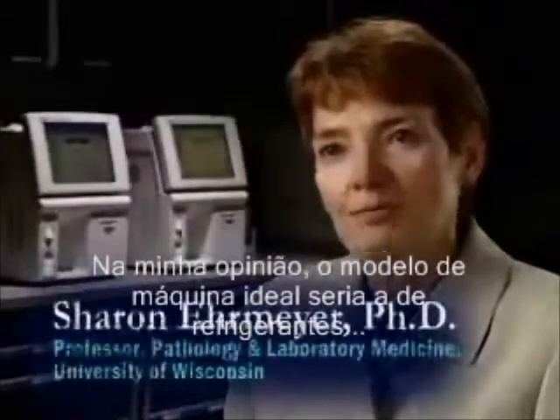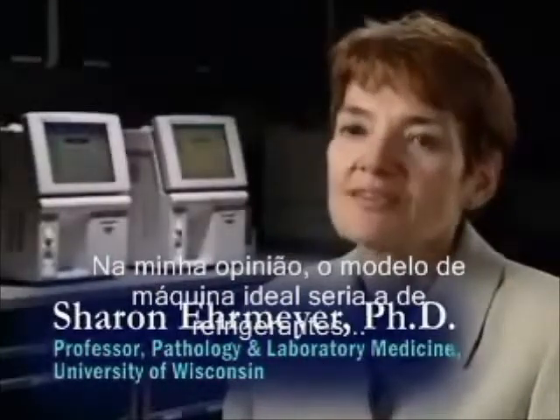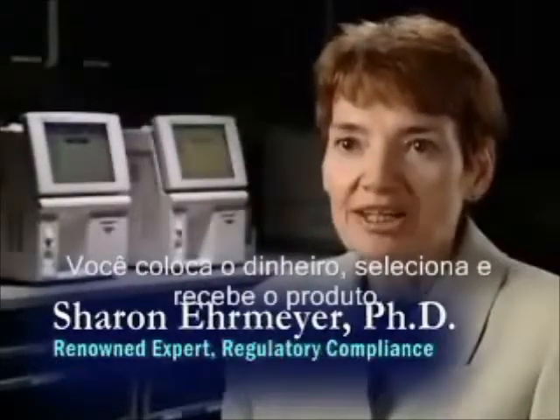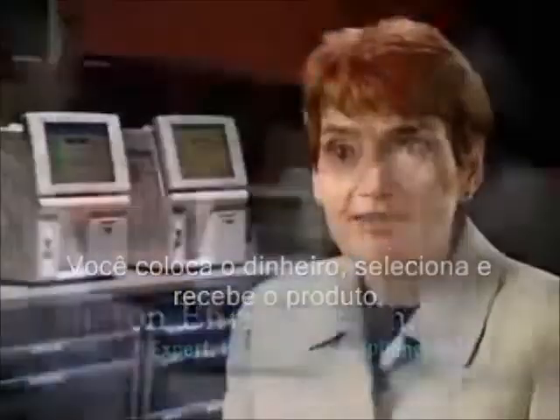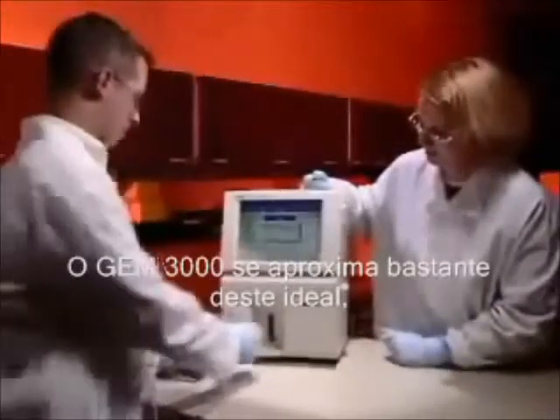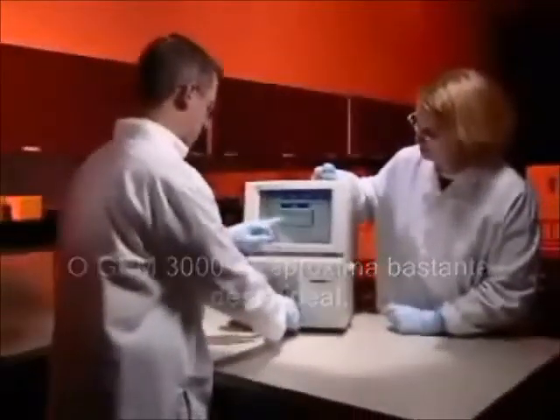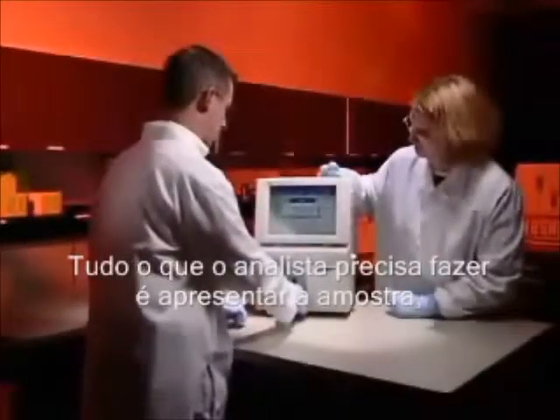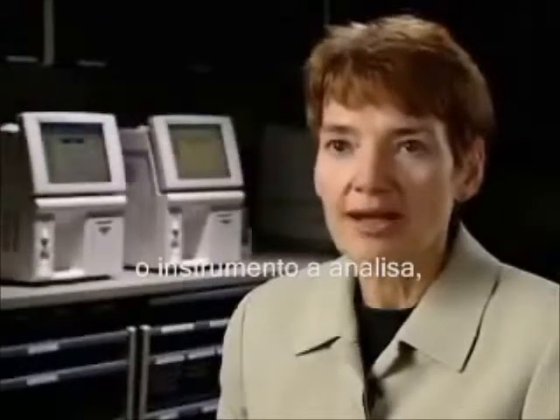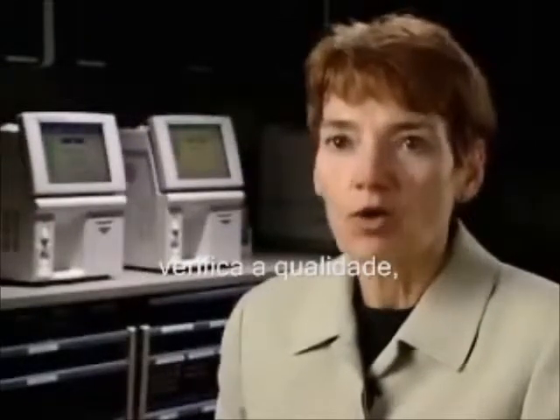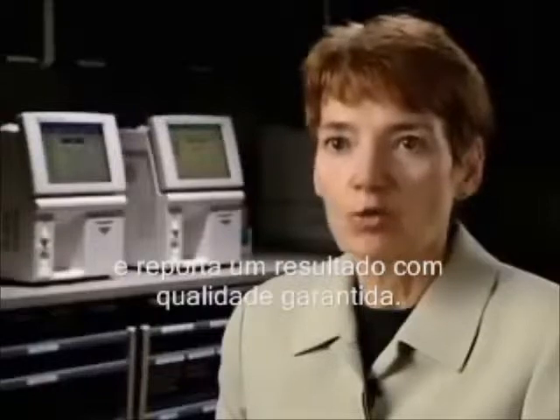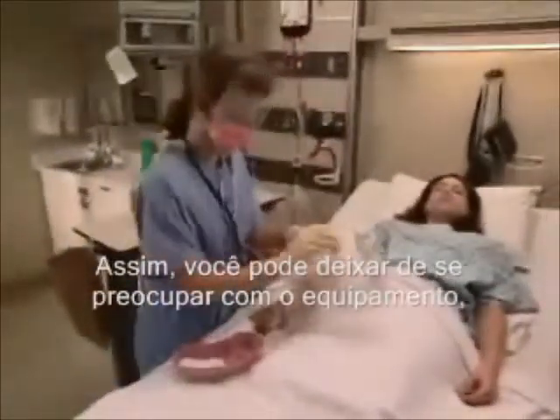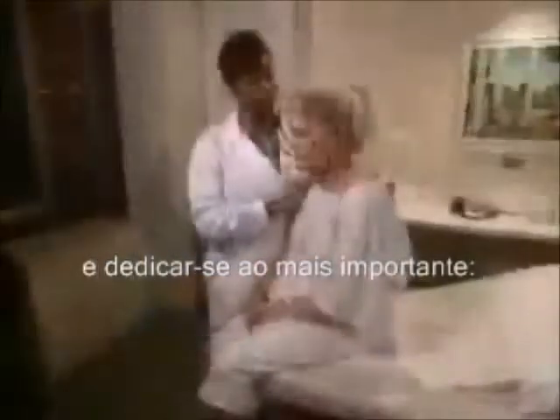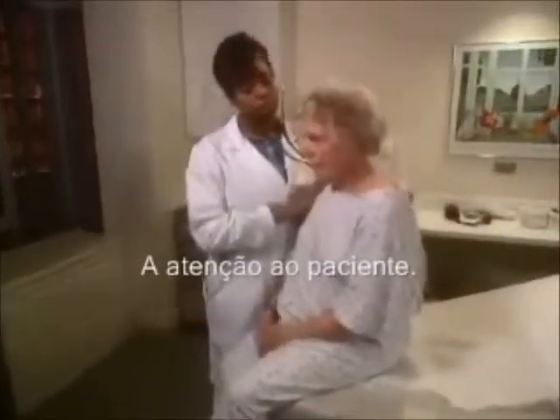In my opinion, the perfect black box for an instrument prototype would be the soda vending machine. You put your money in, you make your selection, and you get your product. The GEM Premier 3000 is certainly very close to the perfect black box. All the analyst needs to do is to present the sample to the instrument, which takes over and does all the analytical processes, makes a variety of quality checks, and generates a quality assured result. So now you can stop focusing on your analyzer and spend more time with what matters most, quality patient care.